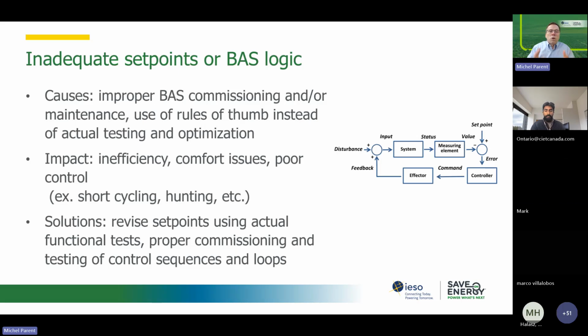So once you've got the right sensor and you still have issues, you may have short cycling. We talked about how short cycling can reduce the life of your motors and your contactors. So you obviously have all of the BAS logic to look after. You want to make sure that there's always deadband in your system and that your PI loops have been optimized. The best way, again, to resolve those possible issues would be to do an EBCx if you could. If not, you have to have a systematic approach, which is usually based on functional testing.